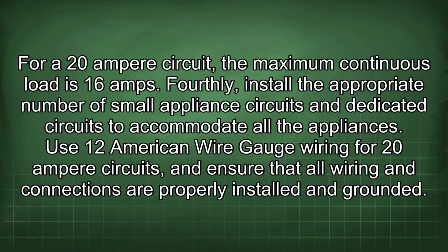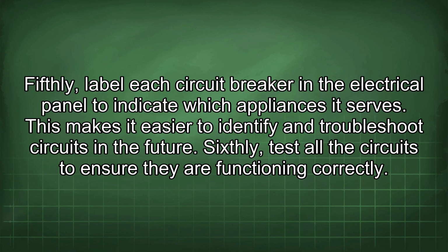Fourthly, install the appropriate number of small appliance circuits and dedicated circuits to accommodate all the appliances. Use 12 American Wire Gauge wiring for 20-ampere circuits and ensure that all wiring and connections are properly installed and grounded. Fifthly, label each circuit breaker in the electrical panel to indicate which appliances it serves. This makes it easier to identify and troubleshoot circuits in the future.